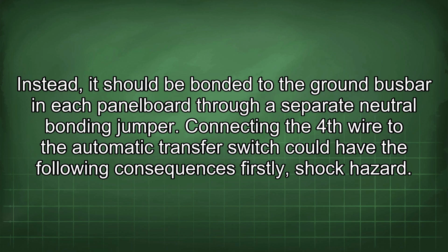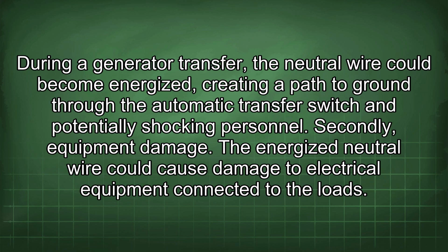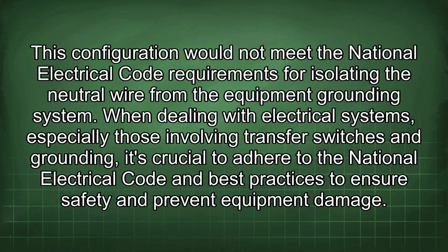Connecting the fourth wire to the automatic transfer switch could have the following consequences. Firstly, shock hazard. During a generator transfer, the neutral wire could become energized, creating a path to ground through the automatic transfer switch and potentially shocking personnel. Secondly, equipment damage. The energized neutral wire could cause damage to electrical equipment connected to the loads. This configuration would not meet the National Electrical Code requirements for isolating the neutral wire from the equipment grounding system.